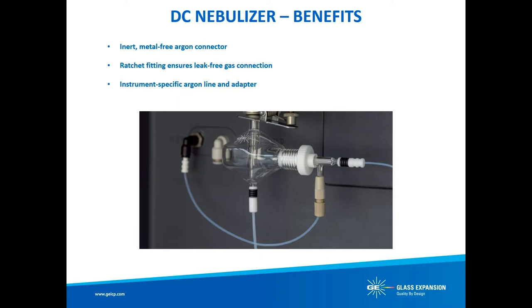We also found that in some cases, when an analyst improperly removed the rigid gas line from the ICP quick-connect, small plastic shavings from the gas line could end up in the nebulizer gas orifice, resulting in irreversible blockage in most cases.